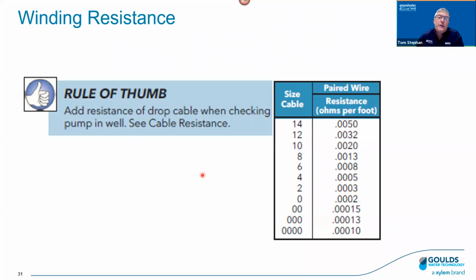And here's where it gets a little tricky, because let's say you want to do this test at the wellhead or at the control box: turn the power off, disconnect, and get into the leads. You can do this, but you're using an ohm meter, so that ohm meter is measuring the resistance of all that wire, all the way down to the pump. So you have to account for that. The book gives you a little chart that says cable size and resistance per foot. If you know what size wire and how many feet, you do the math and then add that to your spec. So this gets a little trickier when you're doing this at the wellhead or at the control box or drive.